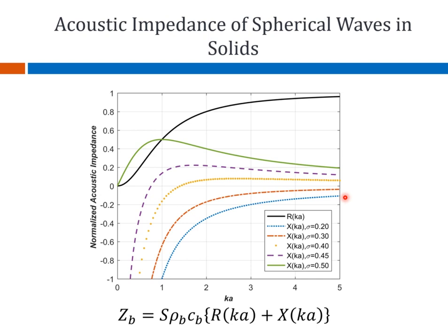It's like a mass-spring system, and the spring is modeled by a capacitance. I mean, each spring has its own Hooke's constant, right? So that spring is much harder to move as compared to what you have at the front of the CMUTs. At the front of the CMUTs, you have a membrane which is more compliant. So at the back, the spring is less compliant. It can be 1,000 times less compliant. So that gives you a very large capacitive reactance. Those values are negative for Poisson ratios less than, let's say, 1/3.